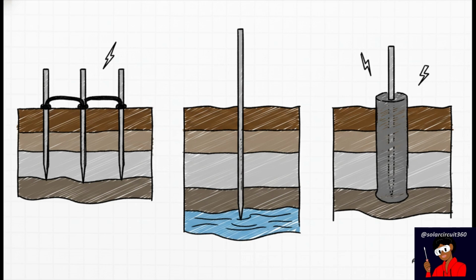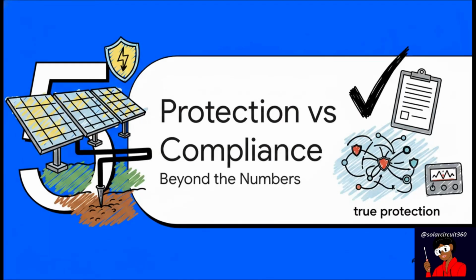They'll drive multiple ground rods, space them apart, and wire them together. Or they'll use specialized equipment to drive rods much deeper into the earth to hit the permanent water table. Sometimes, they'll even backfill the hole with highly conductive ground enhancement materials to artificially lower the soil's resistivity right around the rod.